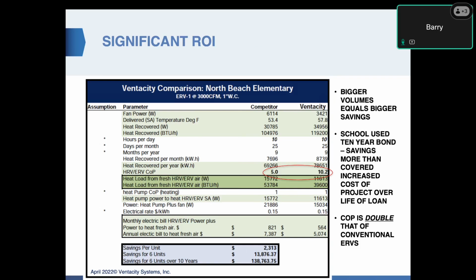The bottom line here is this very high efficiency HRVs were using about half as much energy to provide the ventilation for this school. If you then go down into the chart, we were looking at 15 cents a kilowatt hour in Seattle at the time. And that translated into, over the period of, we rolled that out over 10 years, which was how long they were going to borrow the money, almost $140,000 in energy savings for that school over 10 years. The payback on this, the ROI, was about 3.5 years. So very good for the school on the difference in cost, and they're saving energy continually.